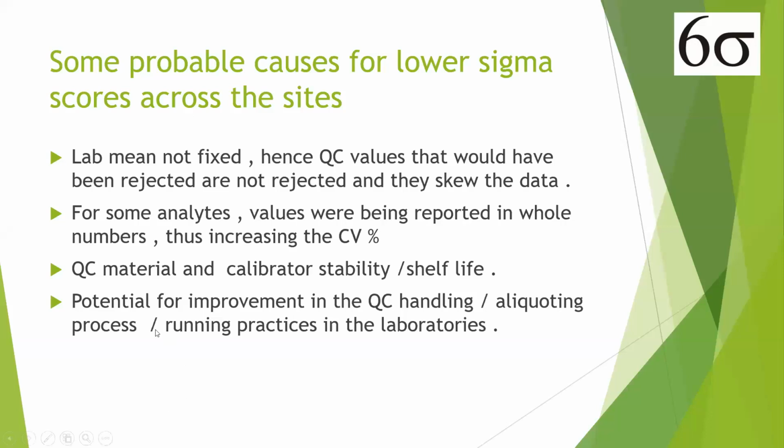Some of the analytes' values are reported in whole numbers. This is a setting in your analyzer and in your lab information system, which was increasing the CV. In some cases, it was the stability and the shelf life of the QC material and the calibrator. We also found that there was potential for improvement in the QC handling or aliquoting processes or running practices in some of the labs.